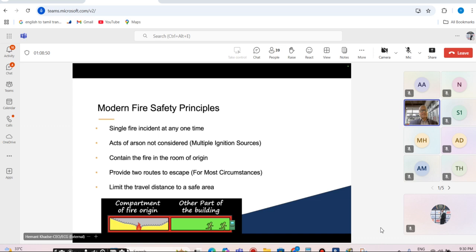But overall, when you design the systems, you always have to look at the fundamentals in the codes and standards, that whatever system you are designing is always based on a single fire incident at any one point in time. It doesn't necessarily have to be that you have two scenarios at one time. It is always a single scenario as the base of your fire life safety strategy. It also doesn't address arson or any kind of deliberate attempt. It is always containment as a first strategy. Means of egress is always a minimum of 2, because in case one is compromised with smoke, there is always a provision to go to the second one.